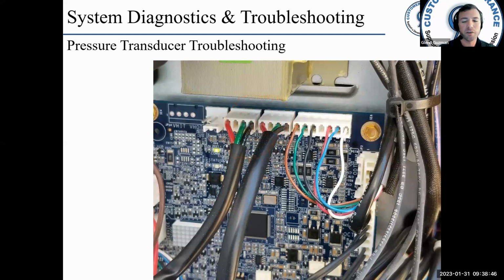Okay, and look on the user interface or on your app. Does the pressure issue follow the transducer, or does it stay wherever it is? So let's say I had an issue with my suction pressure. Okay, and it doesn't matter if it's P1, P2. My suction pressure is reading incorrectly.